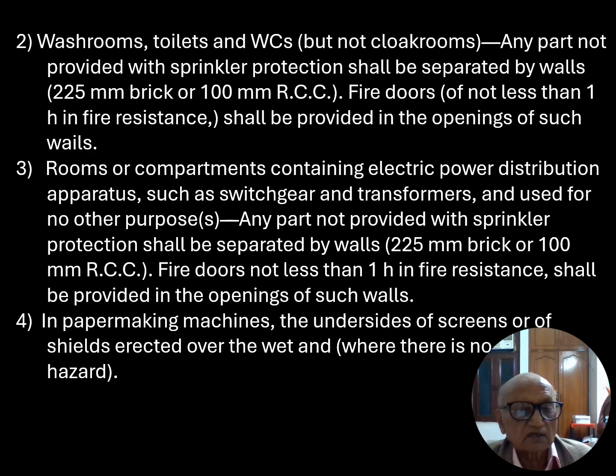Third, rooms or compartments containing electrical power distribution apparatus such as switchgear and transformers and used for no other purposes. Any part not provided with sprinkler protection shall be separated by walls of 225 mm brick or 100 mm RCC. Fire door not less than 1 hour in fire resistance shall be provided in openings of such walls. Fourth, in paper making machines, the undersides of the screens or shields erected over the vat, where there is no fire hazard.